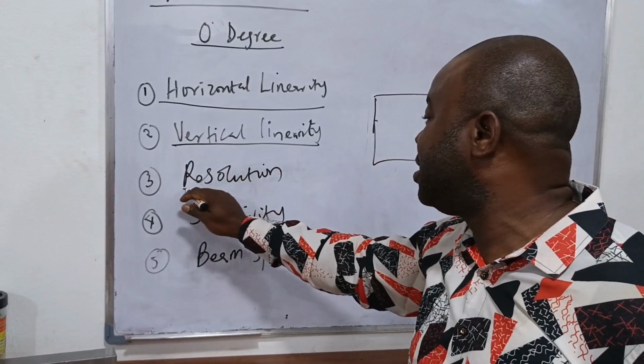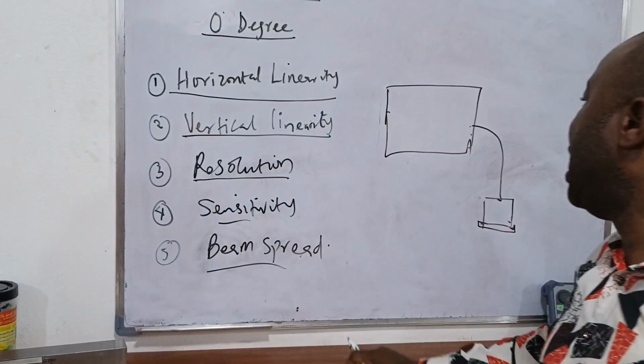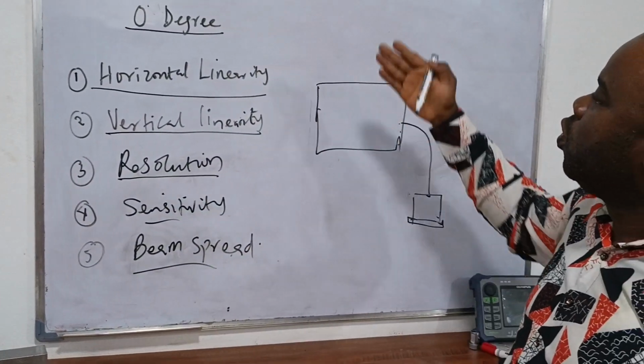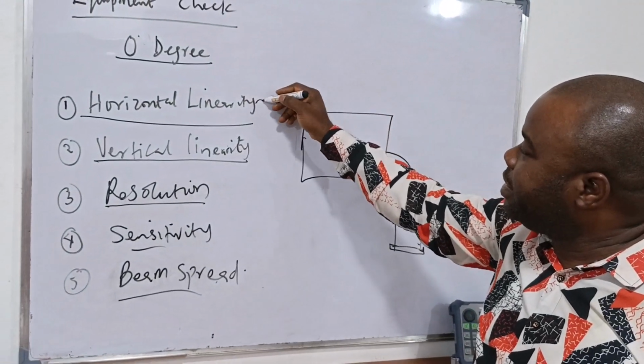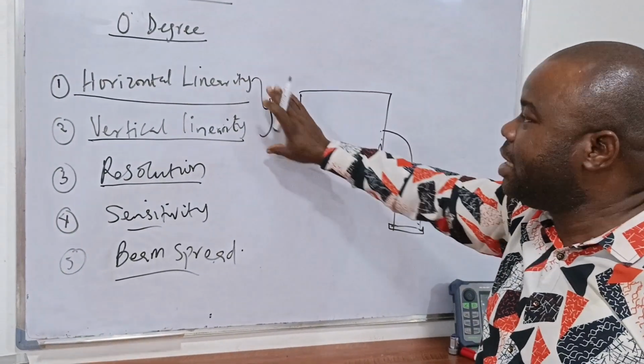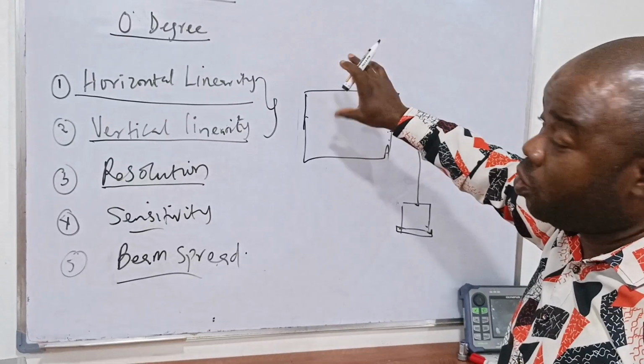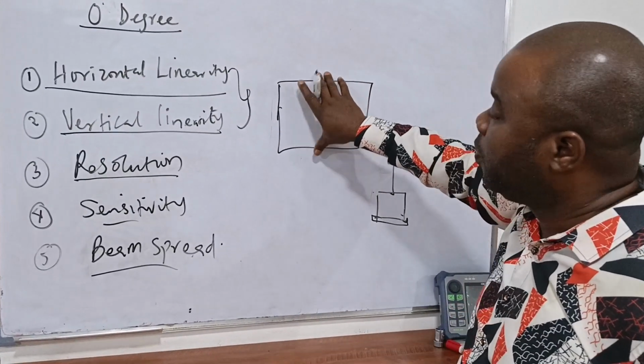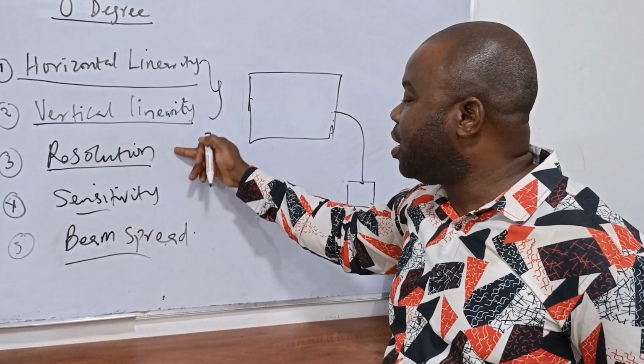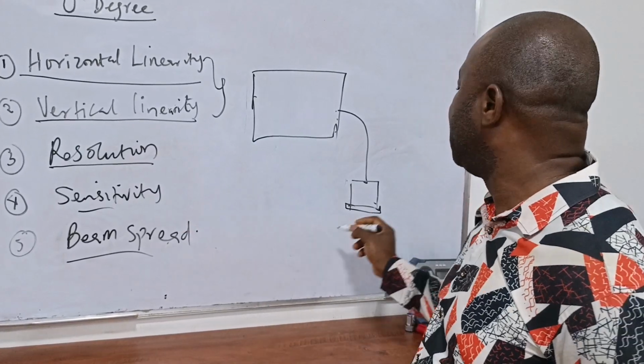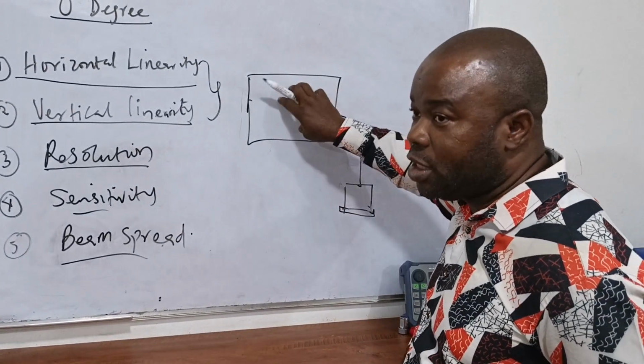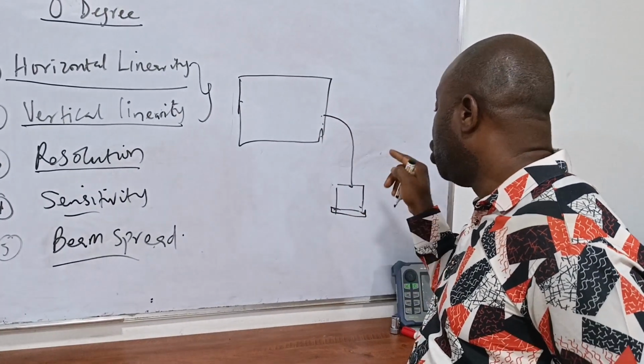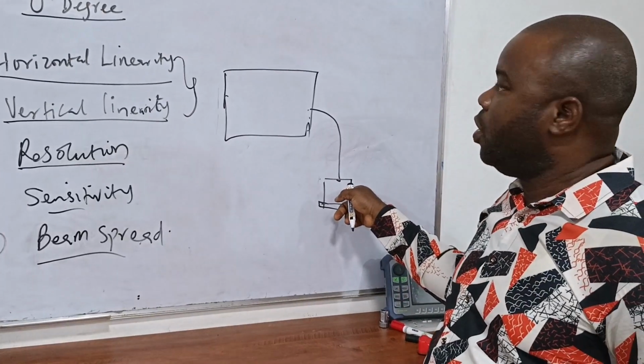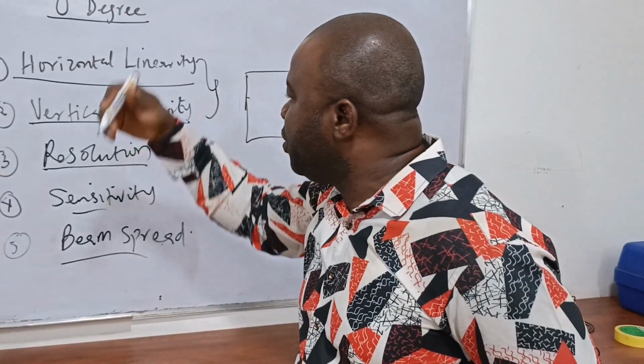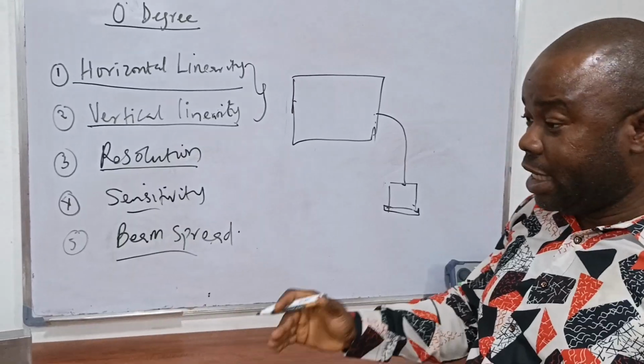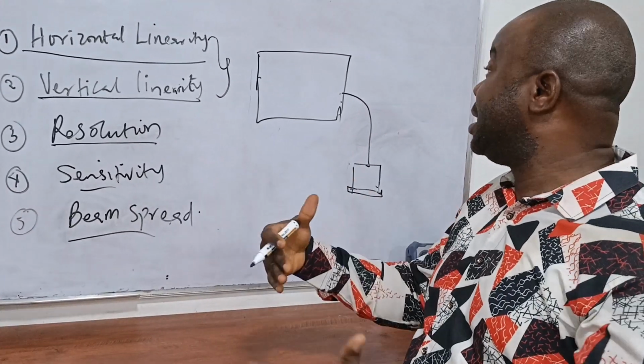We have vertical linearity, resolution, sensitivity, and beam spread. For the two linearity checks, most especially, it is a function of your UT flaw detector. But when we come to resolution, sensitivity, and beam spread, it is a function of not only your flaw detector, but also your probe. So, starting with the horizontal linearity, when you say linearity, it means the equipment is linear.